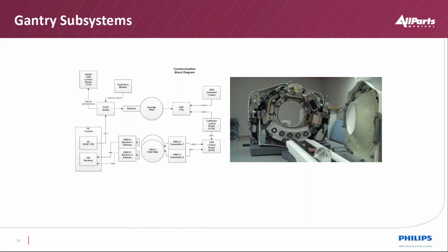So with regards to this slide deck here, this is more of a block diagram view of that scanner with regards to the gantry rotation itself. So we have on the right-hand side the rotating functionality: onboard rotating computer, ORP, X-ray generator control, collimator control, the DAS, and then once that DAS generates a view, the fiber optics would then send that through transmitters over to receivers on the stationary side. We would take that raw data set and then build a volumetric data cylinder that we would then prescribe images out of and reconstruct DICOM type images, okay? That would then be displayed on the operator's console so they would know the progression of the scan, okay? So obviously this is all spinning around the patient. So luckily there's covers to hide all this transactional stuff happening. The patients just hear things whizzing, right?